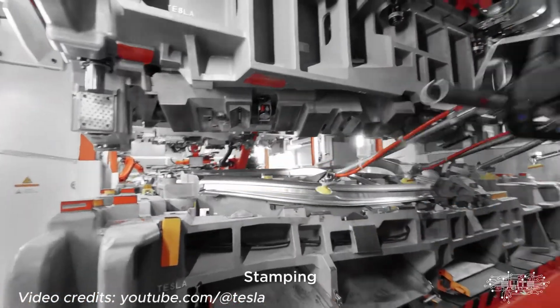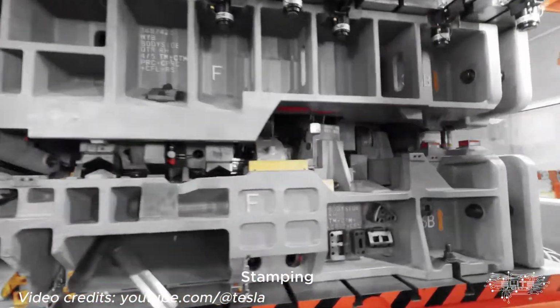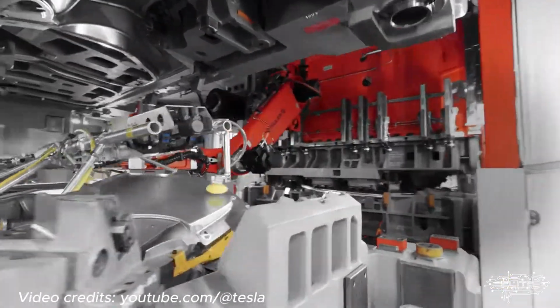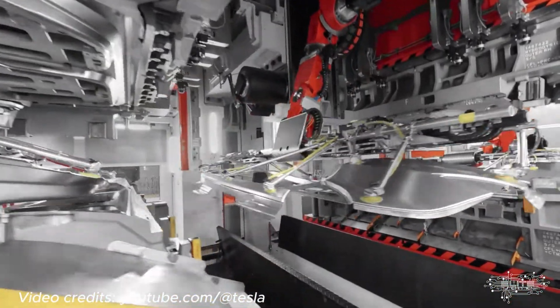You could also have it so that the PLC automatically communicates with the automated system. So it's set up in that PLC where there's an identification between the two, where now the PLC knows the robot system is connected, and now the robot system knows what machine it's connected to. Say for instance, we're talking about stamping presses or something like that. Since it has that identification, it can literally receive the part information directly from the press's part number selection. Even in the automated system, you don't have to go and select a part number independently. What I mean by that is you don't have to select the part number on the stamping machine and then go and select the part number on the automated machine. Literally, you just change it on the stamping machine and it automatically changes on the robot as well.